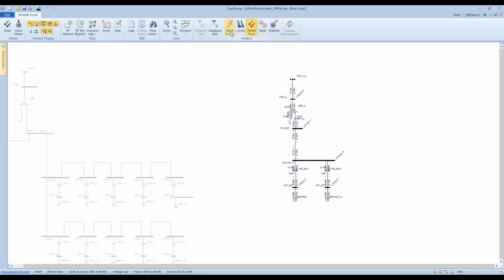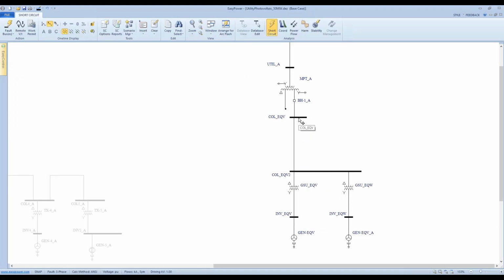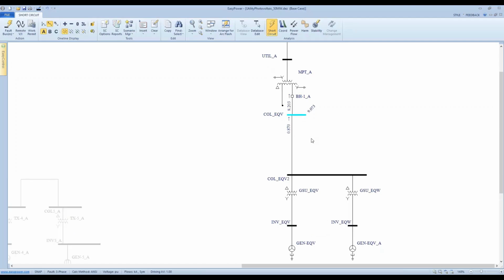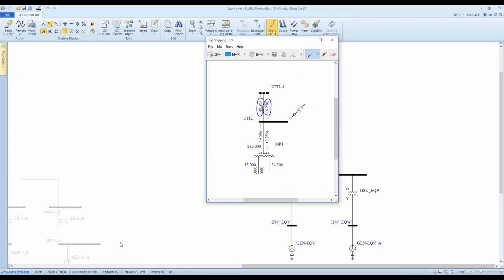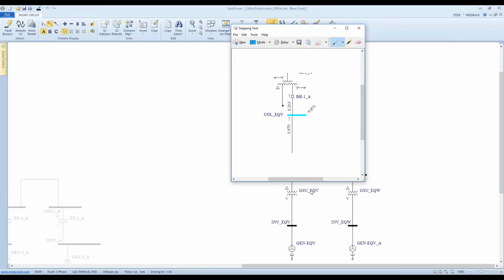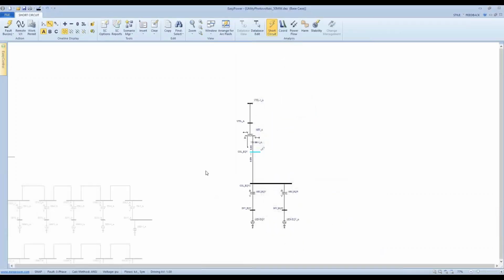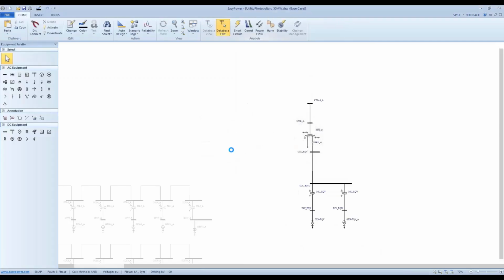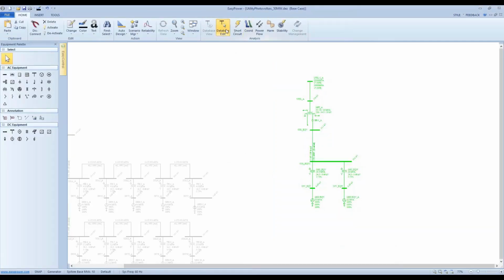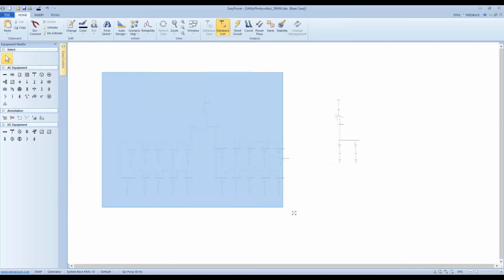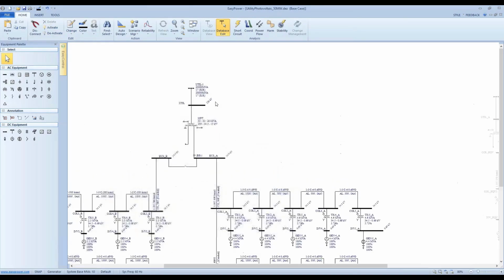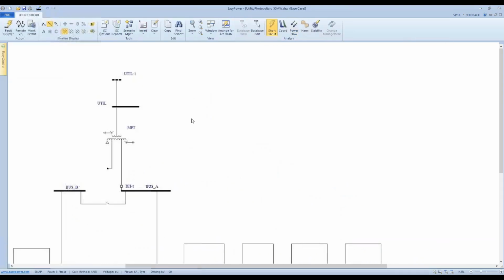Oh, short circuit. Yes, let's do it again. Short circuit. Here, let's say we apply a three-phase ground fault, just a different fault to see if they're the same. Okay, three-phase ground fault at the low side of the main power transformer. 870 comes from the inverters, right? So let's switch to the database. Deactivate the equivalence model and activate the real one line. And let's run a short circuit.